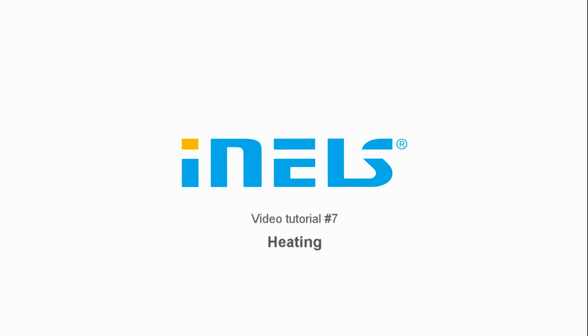The target of this tutorial is to show how you can make a heating or cooling schedule and allocate heating or cooling areas. In this project we use our touch display unit ELKO, which also uses the screen as the thermostat. Because the ELKO unit hasn't got a temperature sensor, we will take the information about the temperature from our wall switch button WSB40, which has an integrated temperature sensor inside. Also, we will use one button on the ELKO unit for the setup of heating mode to the comfortable level.